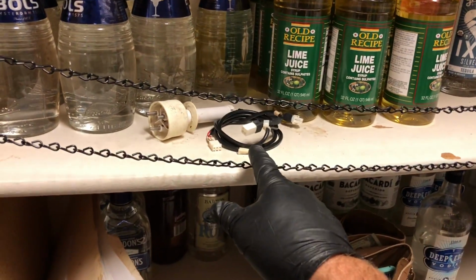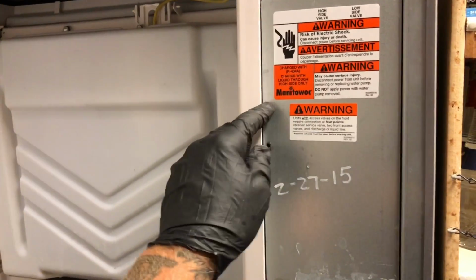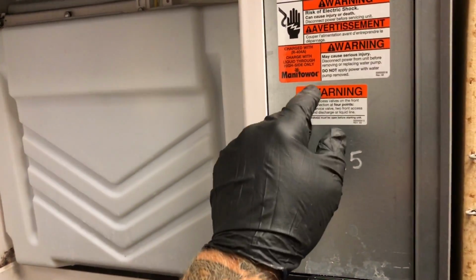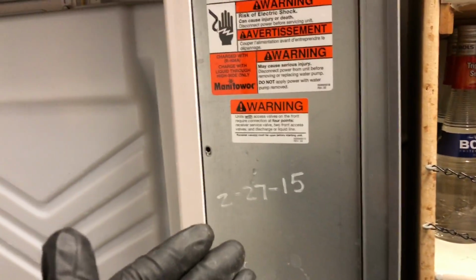Okay, so I went ahead and changed out the water level sensor and the cable because I had them on the truck, and now the machine's working normally. On the old Q and S models, if it would go into defrost with the ice thickness probe off the board, we'd always think the board was bad.